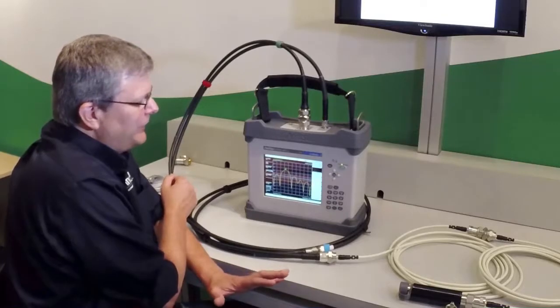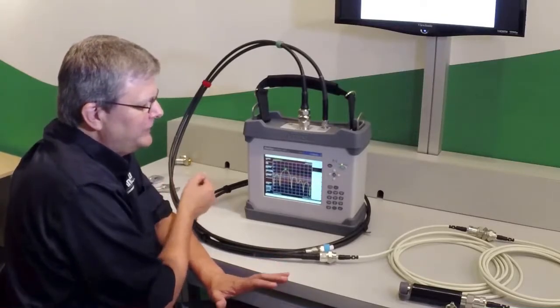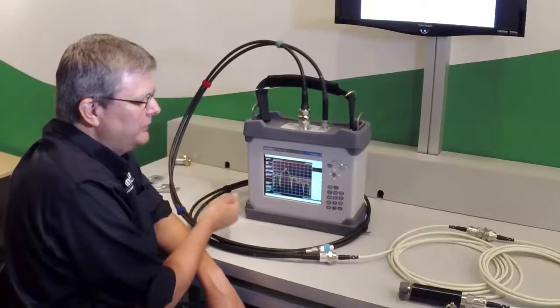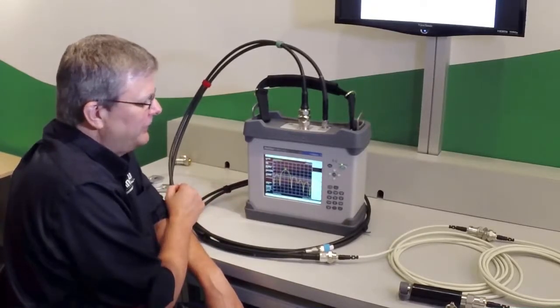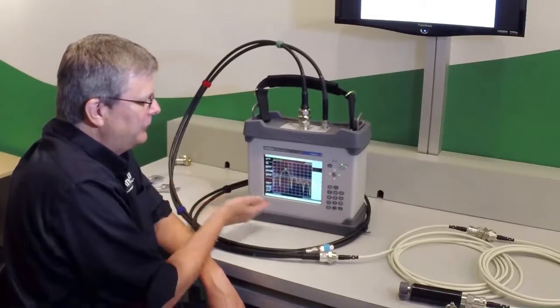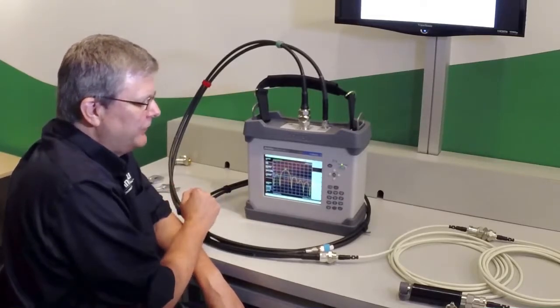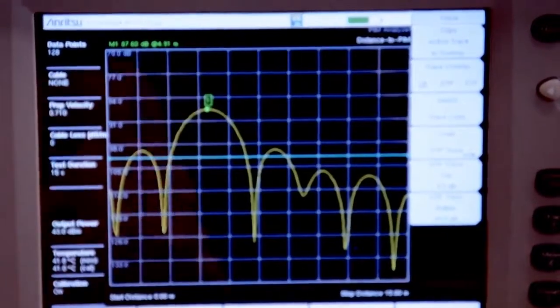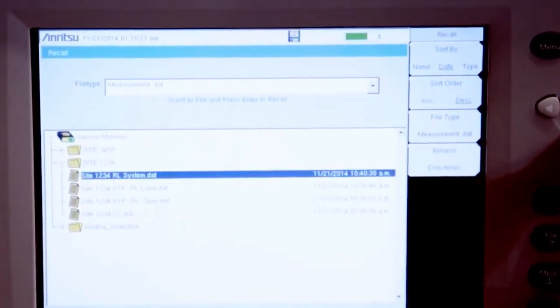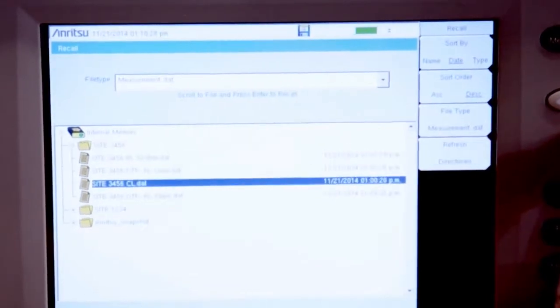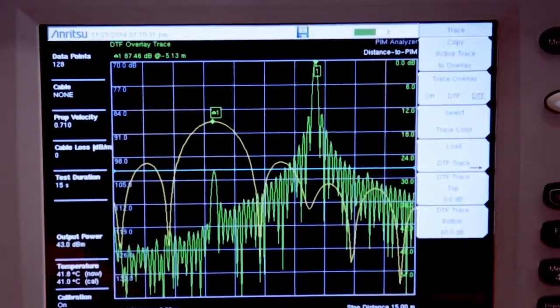A new capability of the B-Series PIM Master is that because we did our cable and antenna analyzer measurements on the same instrument, we can use those DTF measurements we did in cable and antenna analyzer mode to help us gain more information about the location of this PIM problem. So what I'm going to do is I'm going to hit shift trace, load a distance to fault trace, and we're going to go into the site 3456 directory that we were looking at.